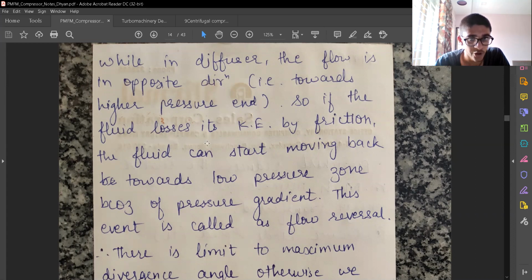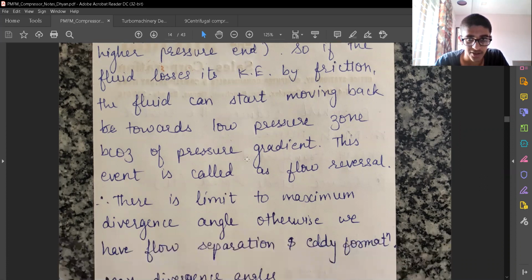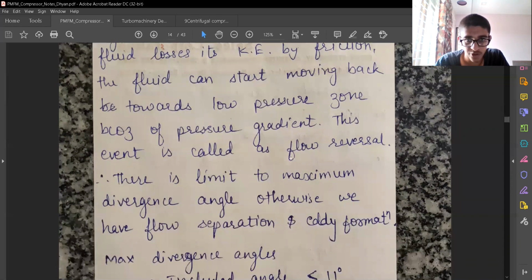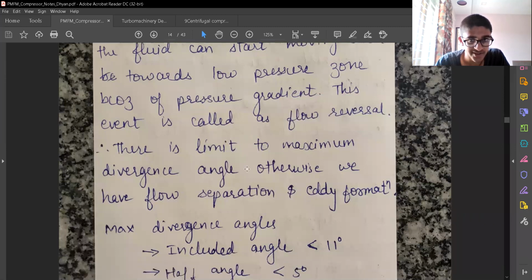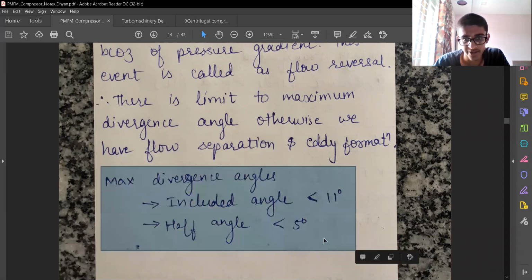If the fluid loses its kinetic energy by friction at the wall, the fluid can start moving back towards the low pressure zone, that is, towards the inlet. This event is called flow reversal. This is a very important concept, flow reversal. Therefore, there is a limit to the maximum divergence angle. Otherwise, we will have flow separation and eddy currents or eddy formation.